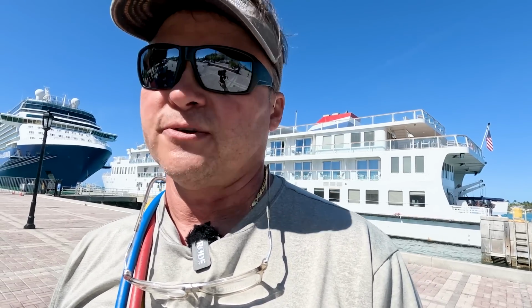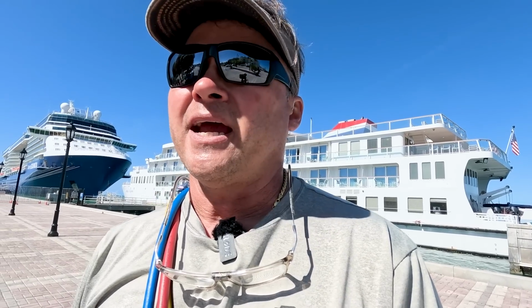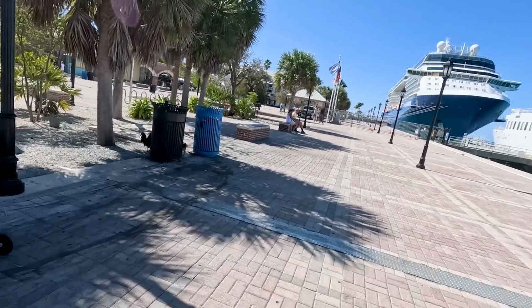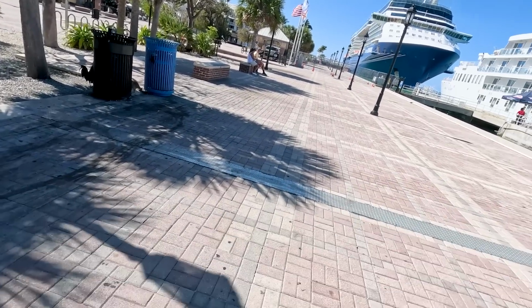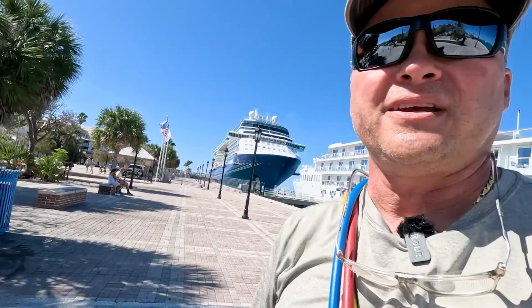But then I noticed a bunch of oil on the deck underneath their saltwater coolers. I found it was at an elbow, and the inside of the elbow had a crack all the way around, a little tiny hairline crack, but that's where the oil kept coming out. So I had to tell them, the only way to fix this is to take the system down, close the valves as best you can, and blow the remainder of the charge out, or recover it. Then you'd have to braze, silver solder, and take that fitting off and put a new one in. They're leaving in 45 minutes, so you'd have to take the air conditioning down.